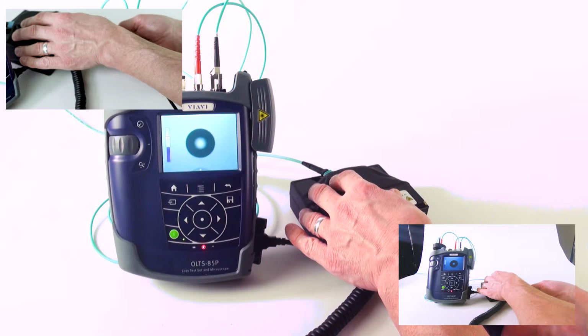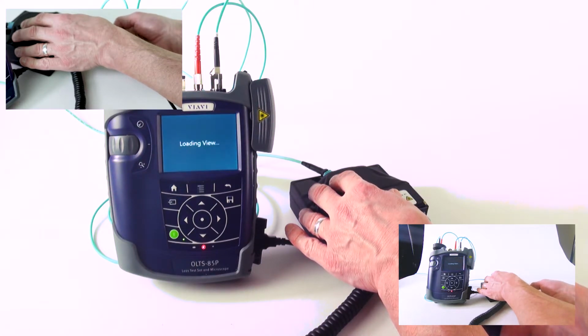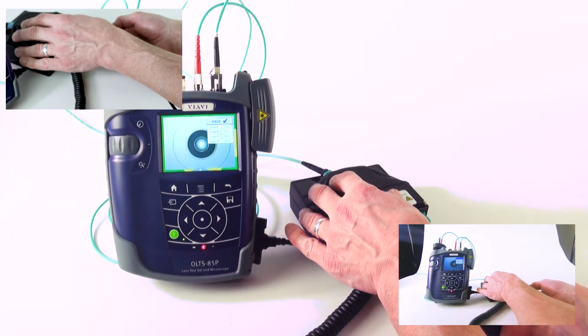So I get a nice, good, strong focus on that, and then I press my pass-fail test button on the probe itself. Don't need to touch the instrument at all. I can do everything from the probe. So it runs the pass-fail for the multi-mode IEC.